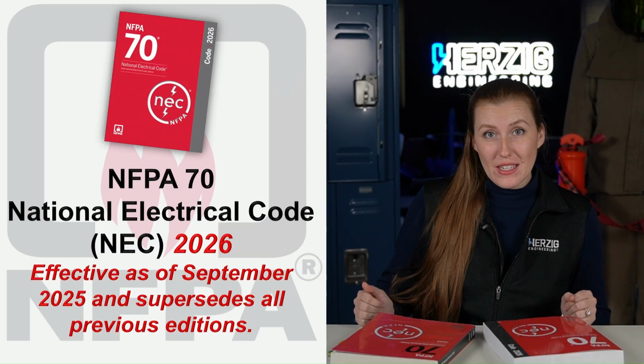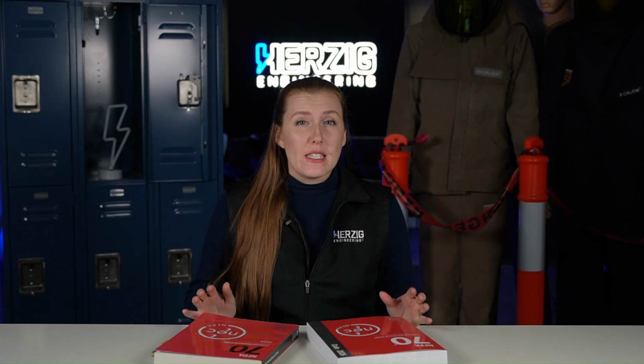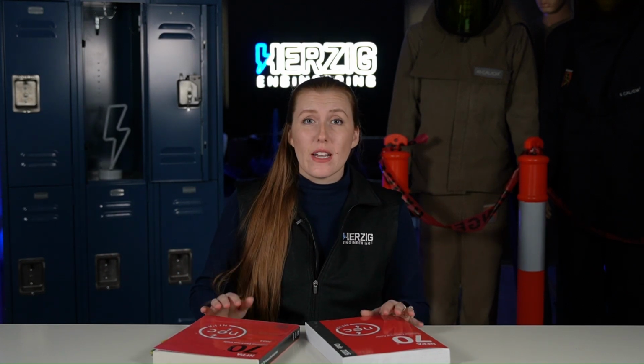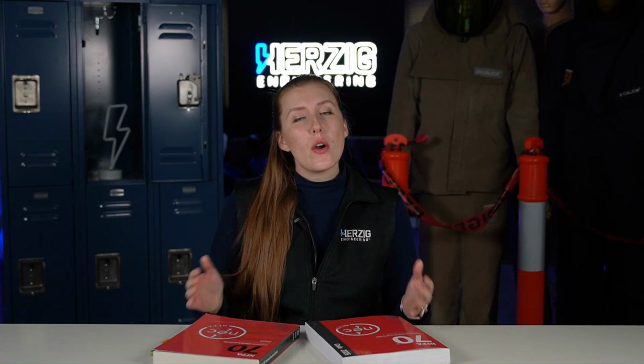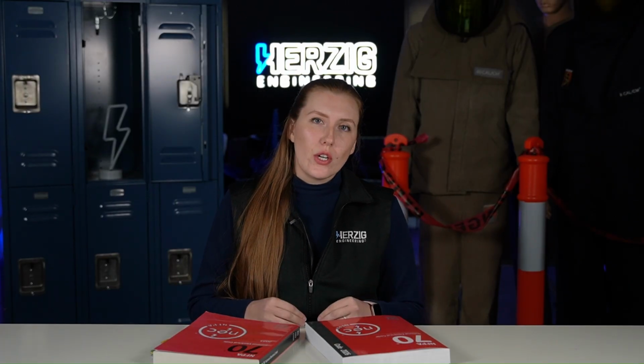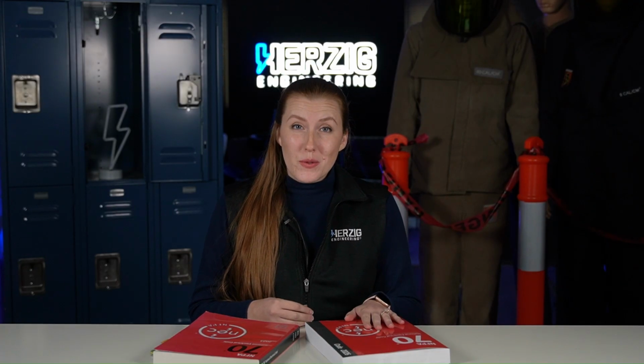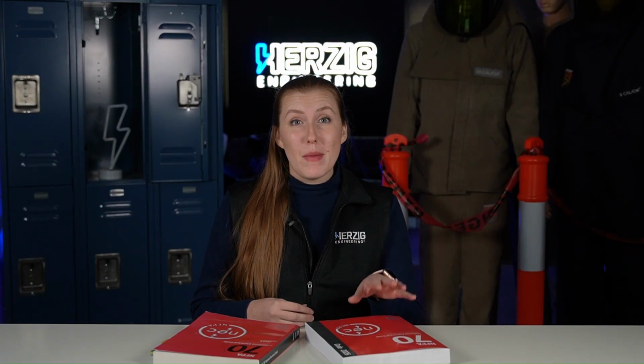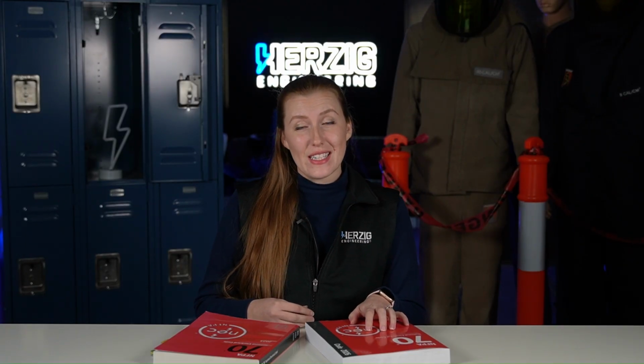flash hazard markings. Now, if you look at the NFPA 70E as your standard for electrical safety in the workplace, we know that this has been a requirement for many, many years. But the National Electrical Code has only mandated it previously for equipment at 1,200 amps or higher. The 2026 edition has made some major changes to 110.16, which we're going to cover in this video today. Let's dive into the code book itself, looking at the 2023 versus the 2026 changes.